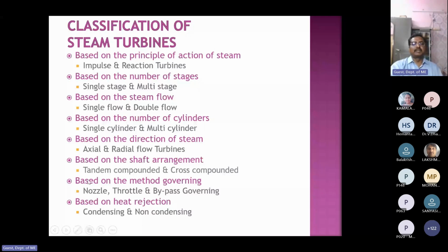Another classification is based on the method of governing. Governing is a very big topic actually. In general, for mechanical engineers, we know the purpose of governing is to maintain constant speed by varying the fuel input. Here it maintains not only speed, it controls the frequency and maintains the load also. So it controls the speed, load, and the frequency.